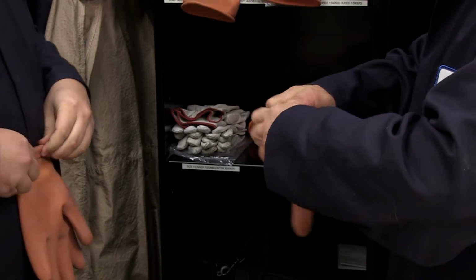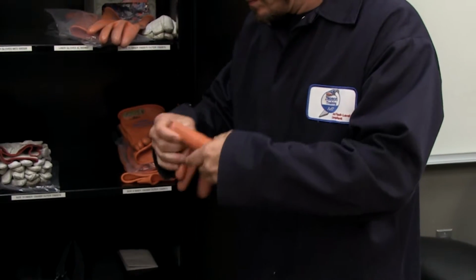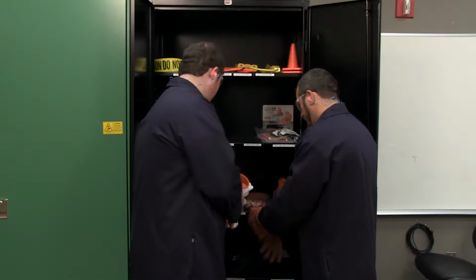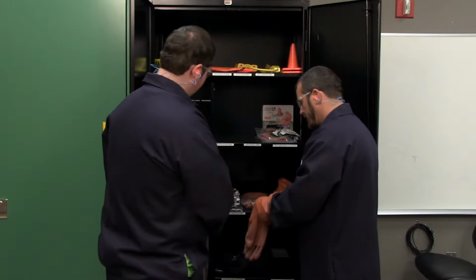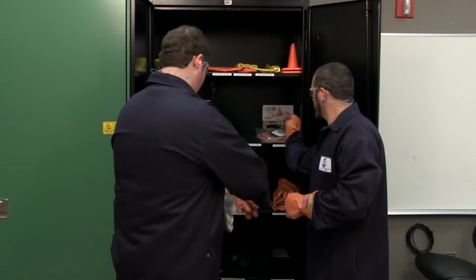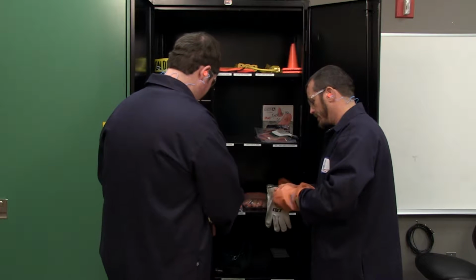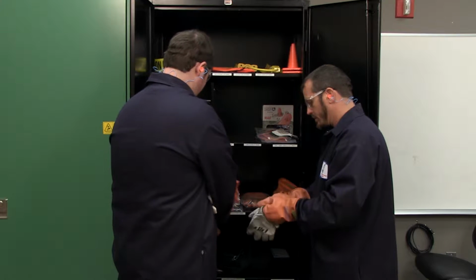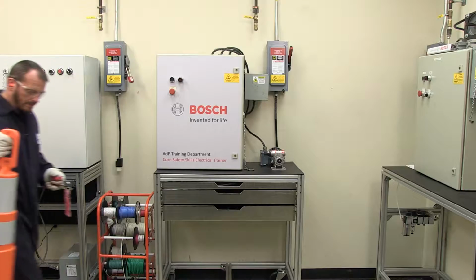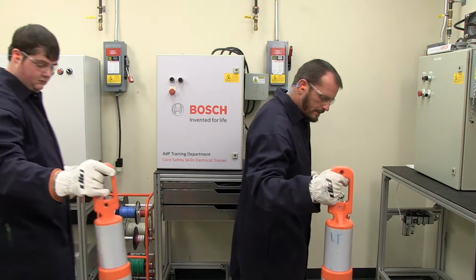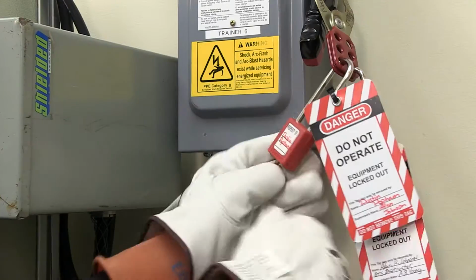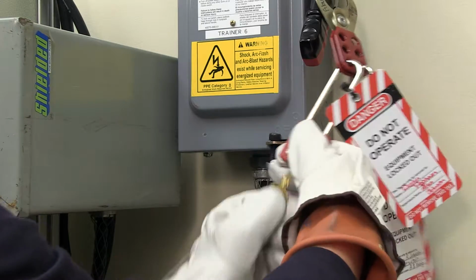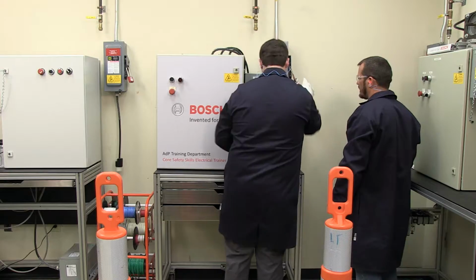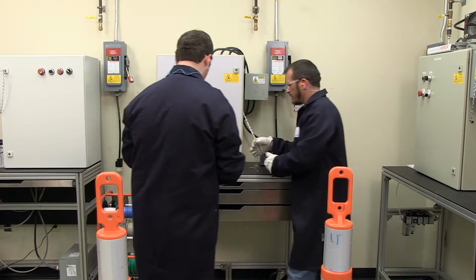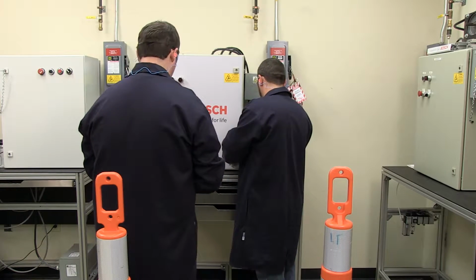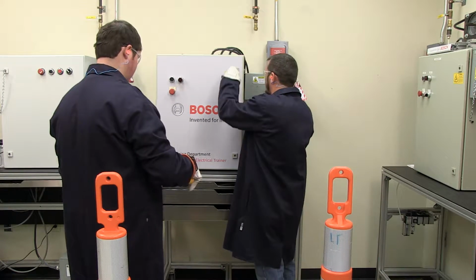To open an energized electrical cabinet of greater than 50 volts, there must be a 2-man team, complete with safety glasses, hearing protection, fire-resistant clothes, leather shoes, 600-volt rated electrical gloves with leather gloves over, and arc flash helmet and shield. An arc flash shock boundary must be established and lockout-tagout performed according to the machine-specific procedure. The PPE may be removed after verification that there is no exposed voltage over 50 volts.